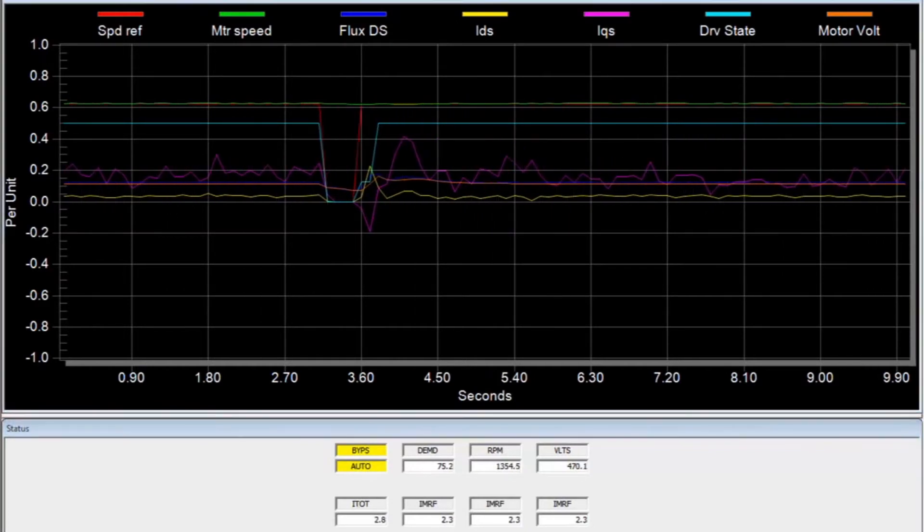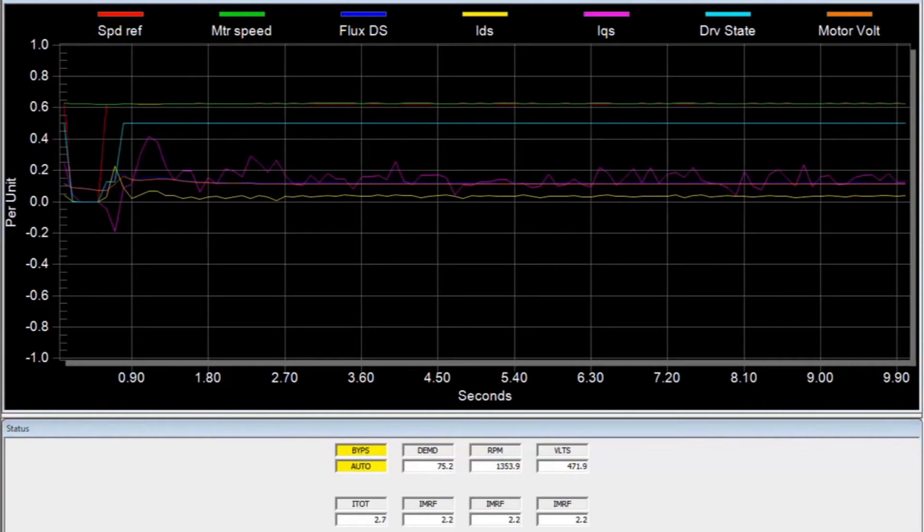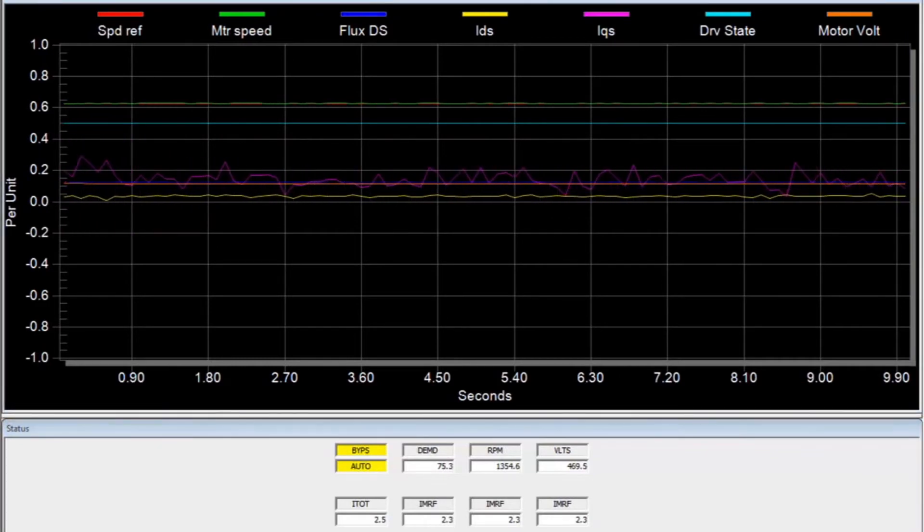Performance is uninterrupted as shown by the constant green motor speed line. In a period of 250 milliseconds, the drive is able to bypass the failed cell and continue to function.